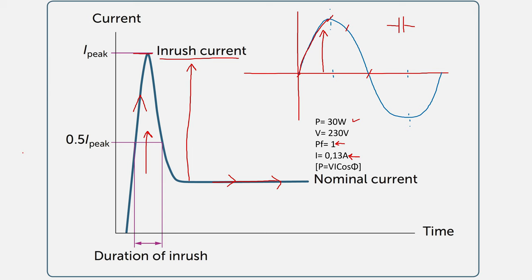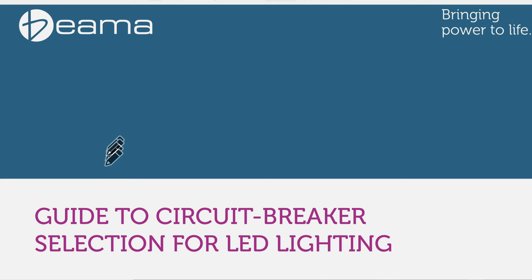But if we turn on the power at a high point in the waveform, we'll see a sudden inrush current, and this is very important because this inrush current can be significantly higher than the nominal current. That's why we need to specify the circuit breakers based on this inrush current.